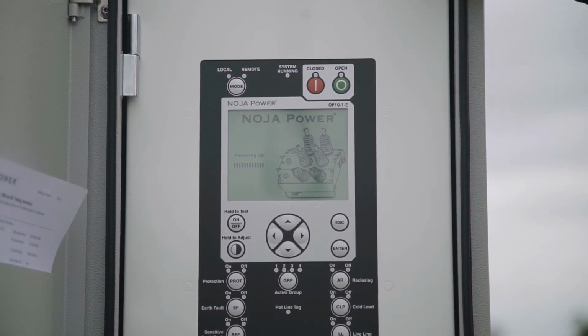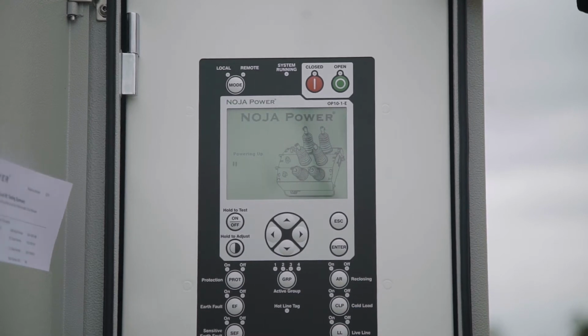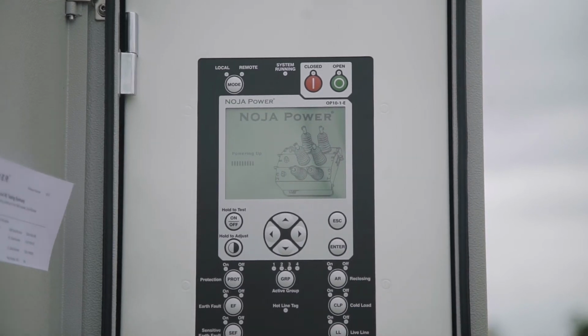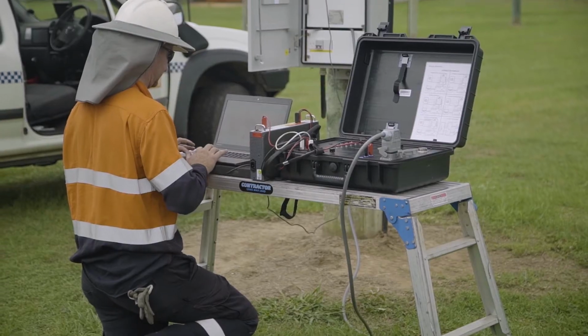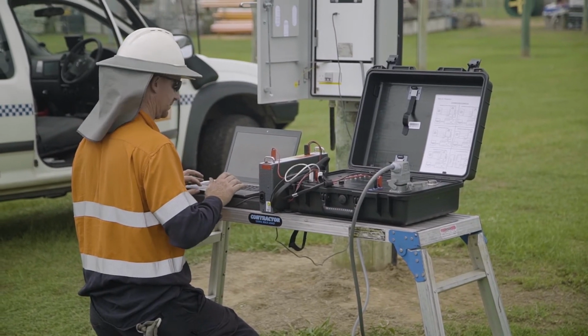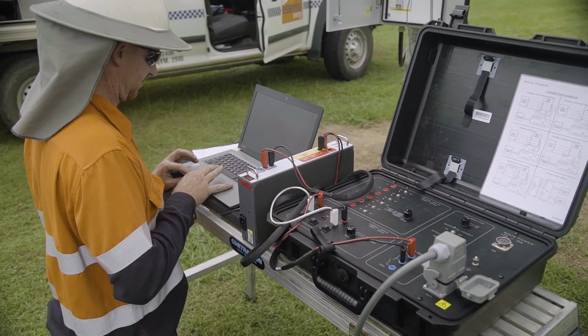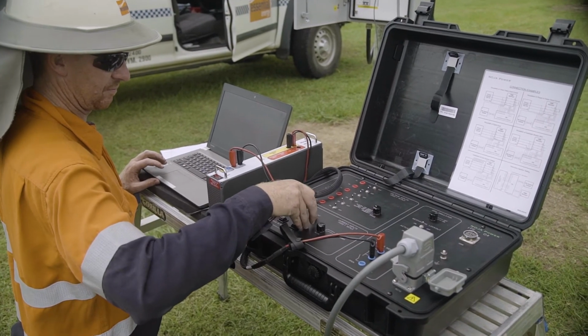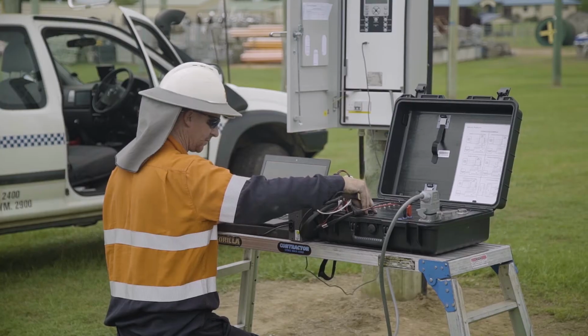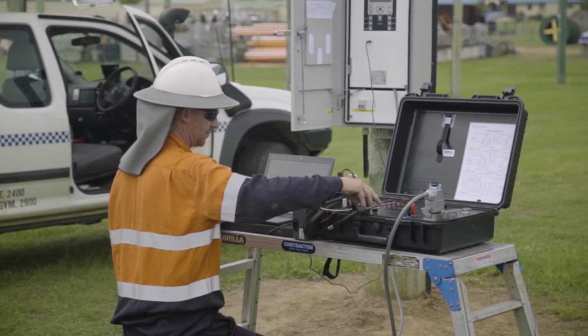If the feeder is energised, check that the voltage and current readings on the panel are correct. Connect to the RC10 with CMS software package and load settings as required. Conduct any other commissioning tests as specified by local regulations and requirements.